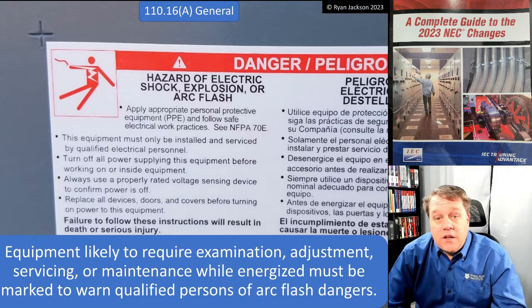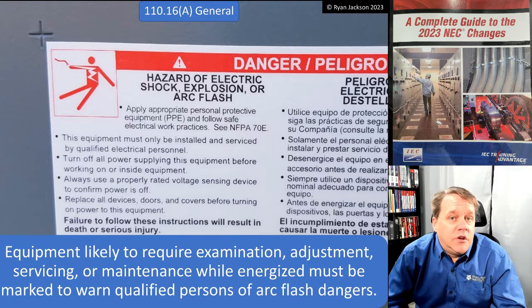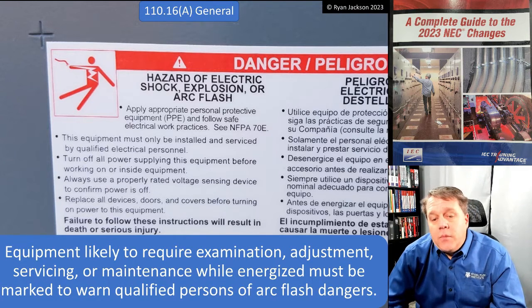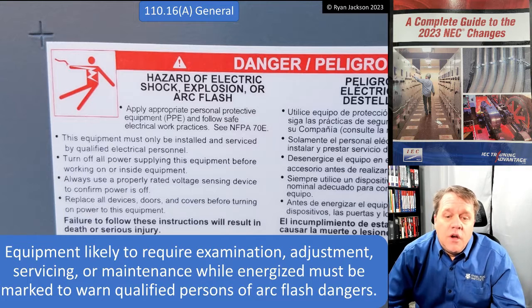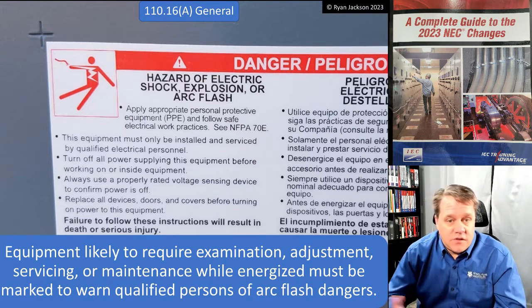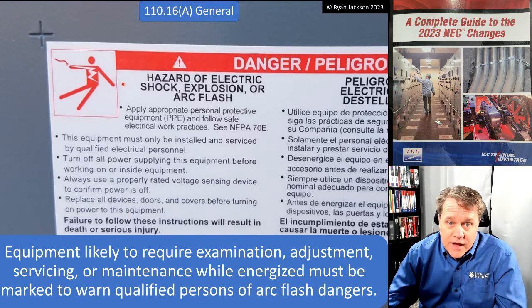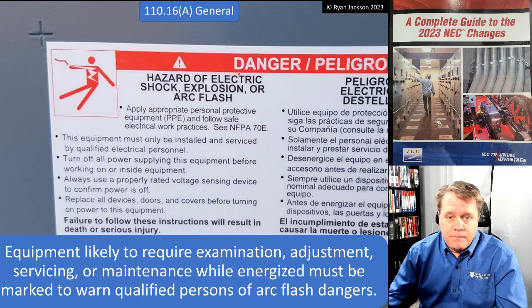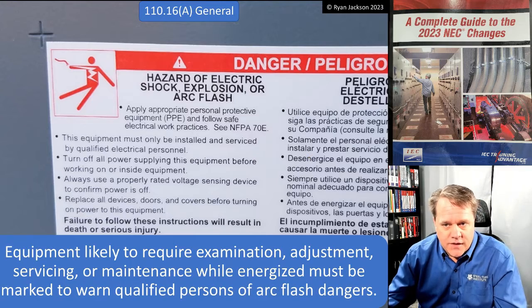110.16(A) didn't change. It says, look, equipment likely to require examination, adjustment, servicing, or maintenance while energized must be marked to warn qualified persons of arc flash dangers. All right, so here is this sticker. This is all you have to comply with the code. Warning, arc flash. All right, that's it.